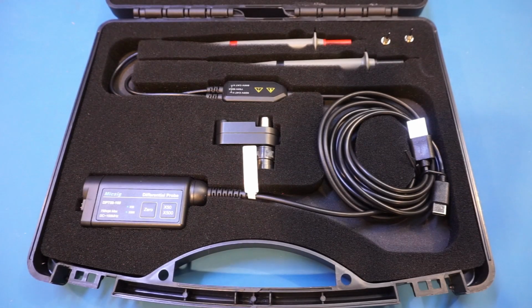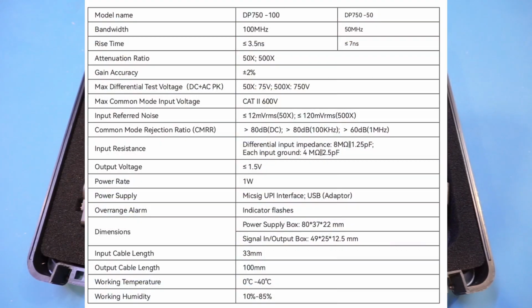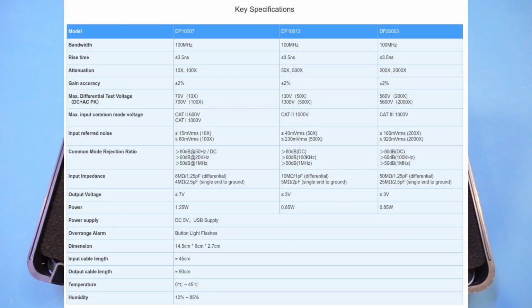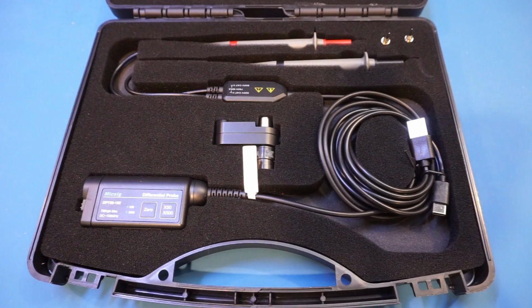Spec-wise, this high voltage probe is similar to that of the DP100-07 in the DP100 series. Both have a bandwidth of 100 MHz. The 100-07 measures up to 700 volts, which is comparable to the 750 maximum voltage this probe can measure. Other areas are also similar, but you can definitely see there are some improvements on this newer 750 version.